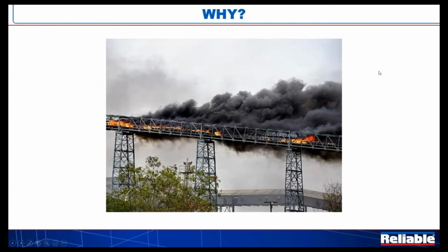So another reason why, well, oftentimes we're moving materials across areas that we simply can't get to. This is a very good picture of an elevated conveyor that happens to be in a pretty bad state at the moment. But not only do we have materials that are engaged in a fire that we can't get to, but they're also moving typically horizontally or diagonally up and down. Now we've got this case where we're actually moving a fire potentially either into a building or another process application. So what are we looking at here?